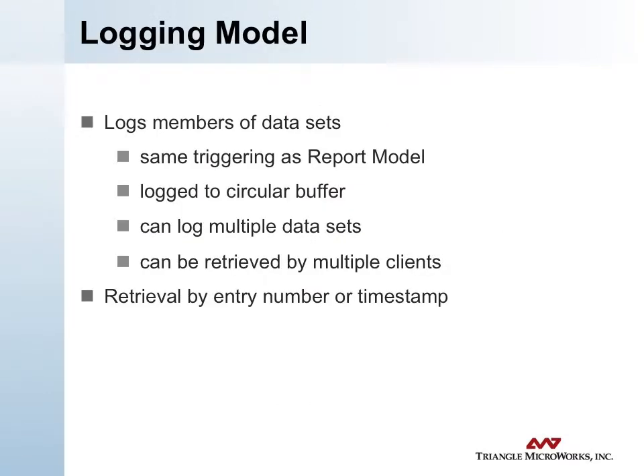The logging model within 61850 works very much the same as the reporting model. Values from the sequence of changes of data within the data set are logged using the same triggering as the report model. It's logged to a circular buffer, typically much larger than the reporting model. You can log multiple data sets into one circular buffer by using multiple log control blocks all pointing at the same buffer. Multiple clients can receive this log — it's open to requests from multiple associations at the same time — and you can retrieve values from that log either by entry number or time stamp.